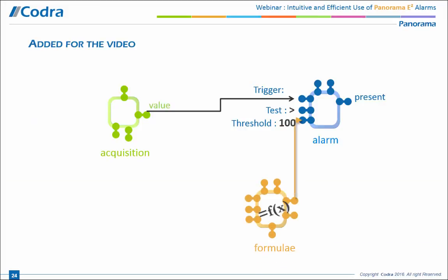For instance, if you want your different thresholds to correspond to a hysteresis function, like a threshold causes the alarm to appear, and then you modify the threshold so that it only disappears with a low value, so that it avoids alarms always appearing and clearing. A formula can be used easily for that. It would use a test like: if alarm present, then use 90 as threshold, otherwise use 100.